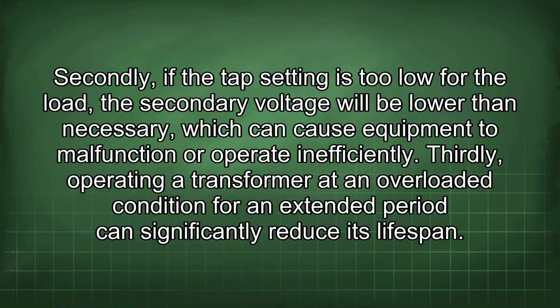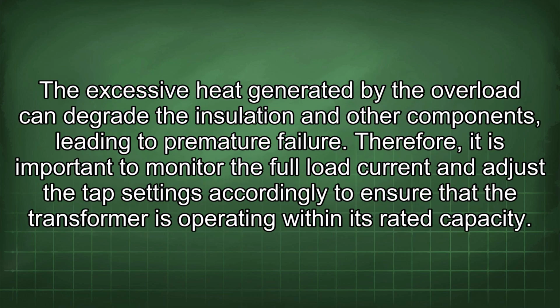Secondly, if the tap setting is too low for the load, the secondary voltage will be lower than necessary, which can cause equipment to malfunction or operate inefficiently. Thirdly, operating a transformer in an overloaded condition for an extended period can significantly reduce its lifespan. The excessive heat generated by the overload can degrade the insulation and other components, leading to premature failure. Therefore, it is important to monitor the full load current and adjust the tap settings accordingly to ensure that the transformer is operating within its rated capacity.